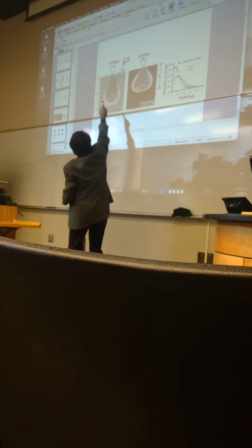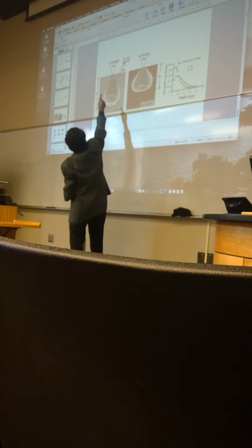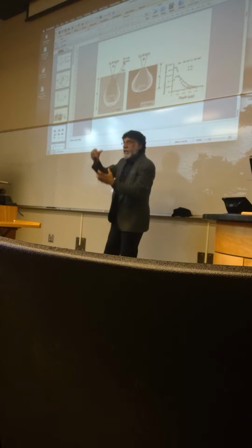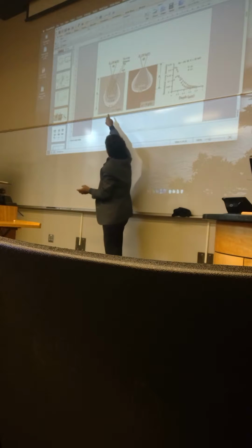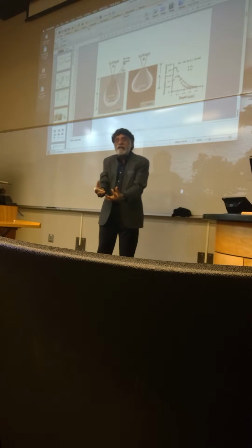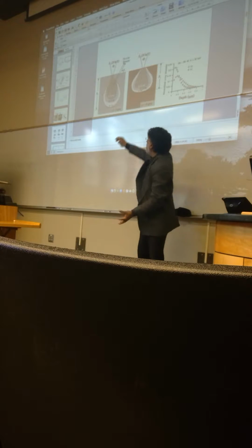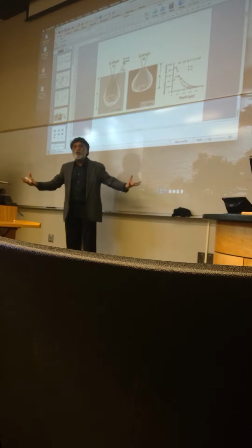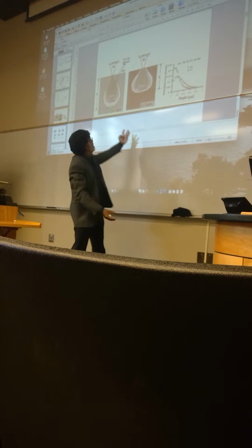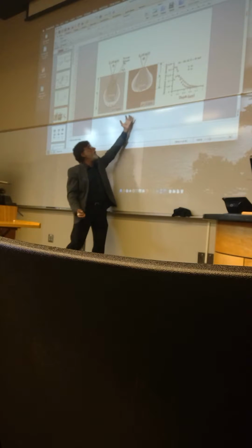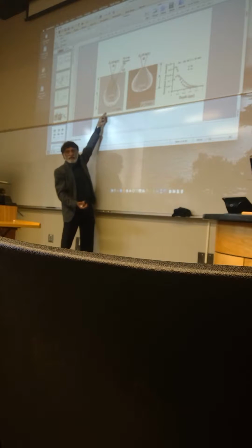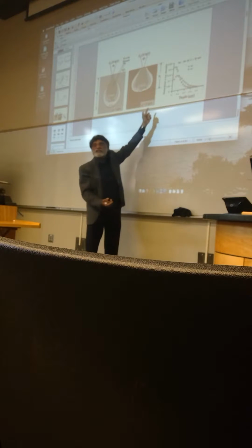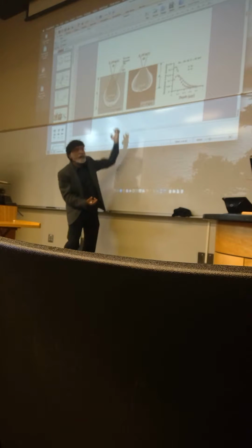So if you look here, as it is losing energy, the dark gray area is where it has enough energy to excite a copper K alpha. Then it loses more energy, and then it has only sufficient energy to excite the aluminum K alpha, which is much lower energy. And then it loses all its energy and it becomes zero. Just then, there's no more energy to propagate in the material. And the same thing is shown on this side. The only difference is the density of this material. The density is 3 grams per cc. This is 10 grams per cc. And since this is more dense, it has less depth that it can propagate.